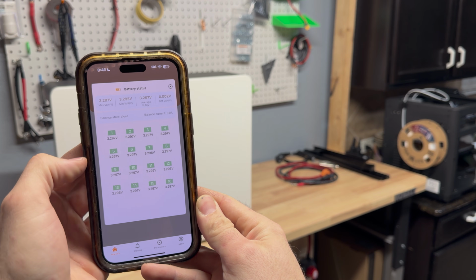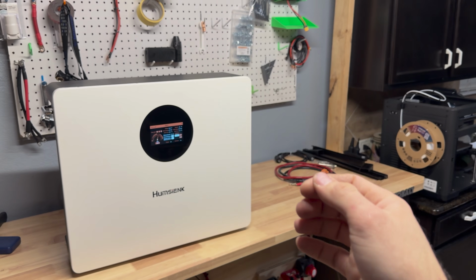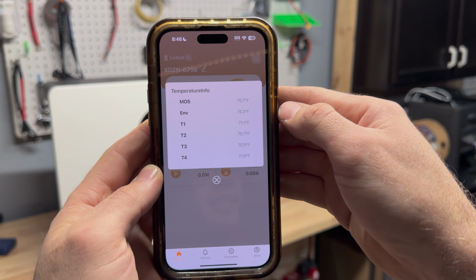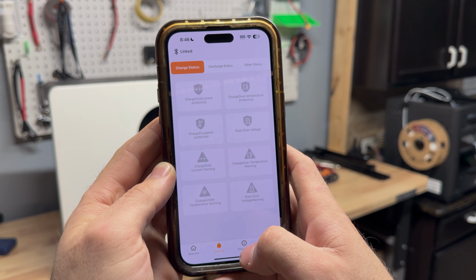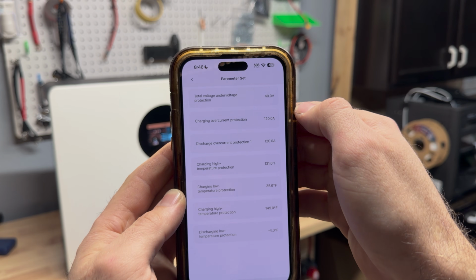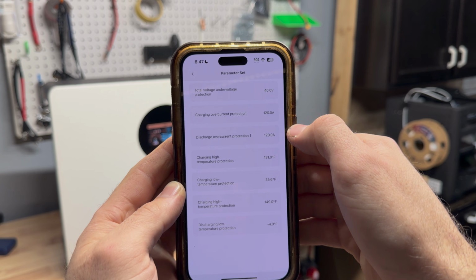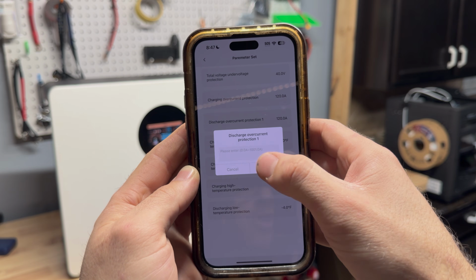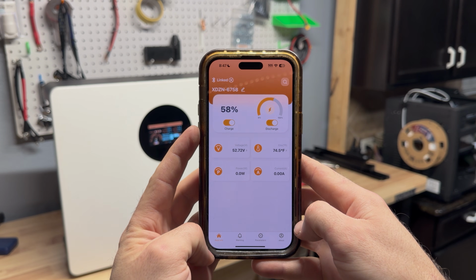You can click on this and see all your cell voltages just like on the little display, min and max. All your temp sensors, it has 6, power, current, you have your warning page, parameter page, go to parameter settings, gives you all the information there. It looks like the overcurrent is actually set to 120 amps, and you can go in there and change that. Pretty cool, not much more to it.